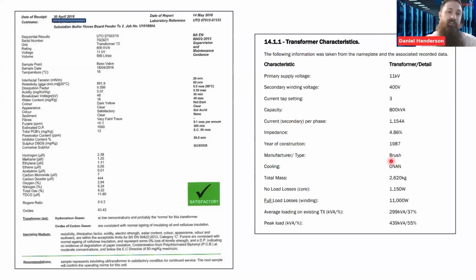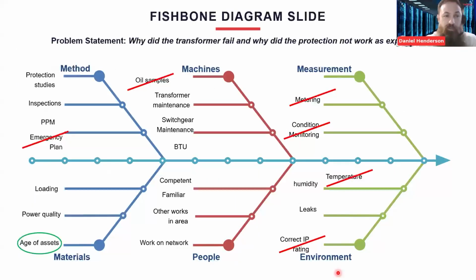And this is the latest oil sample result, which was, what was that, two months, a month before the failure. Again, there's no indications of anything; it's aged in line with the age of the asset. Nothing stands out there to say there's anything wrong. So from that side, I'll probably drop off the oil sample side of it, but maybe keep on age of assets. Possibly it's a consideration, but nothing indicated that it was degrading to that point.